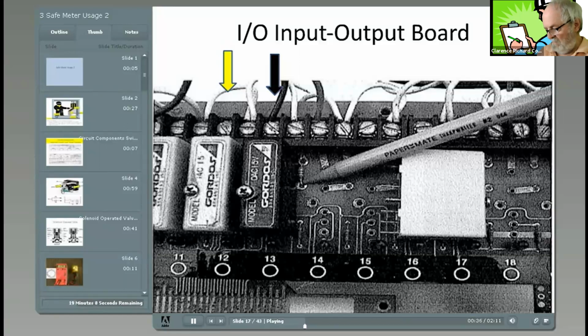colored input modules. The black modules are 120 volts AC relays with contacts that energize when the corresponding LED illuminates. When the contact closes, the black wire above it has 120 volts AC power to the terminal with the black wire on it, the terminal just above the black module. The black modules are probably used to energize solenoid valves to open gates and valves. If the LED lights up, the computer is asking that module to energize the solenoid valve.